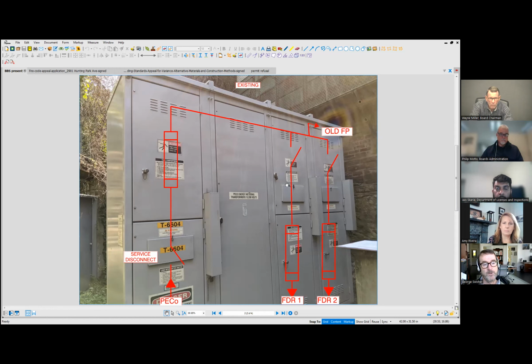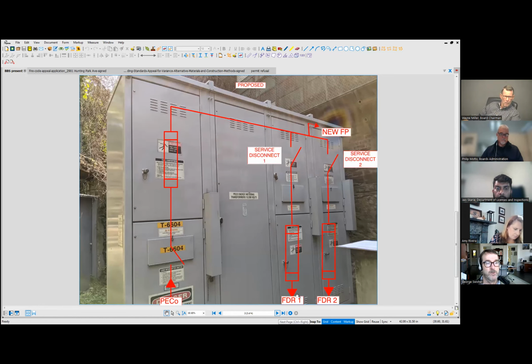As presently configured, the main switch is considered the service disconnecting means, and there are two feeders. One feeder feeds the building, and a second feeder feeds a spare pad-mount transformer that's not in use right now. What we are proposing is to call these two switches the service disconnecting means, and maintain the connection to the fire pump. That way, when first responders report to put out the fire, they can come to the switchgear, throw these two switches, the building is de-energized, but service is still maintained to the fire pump.